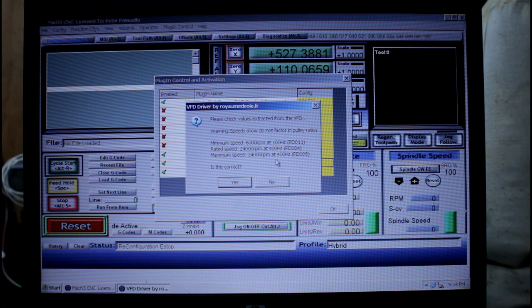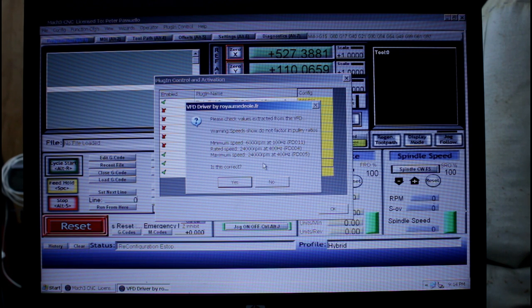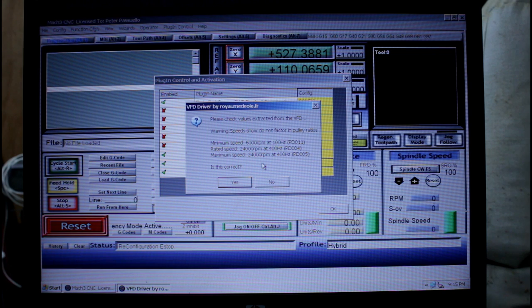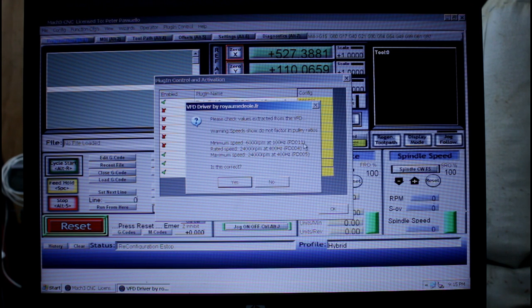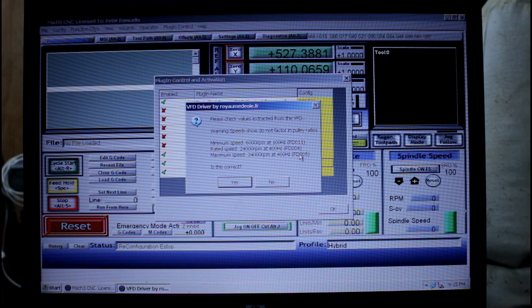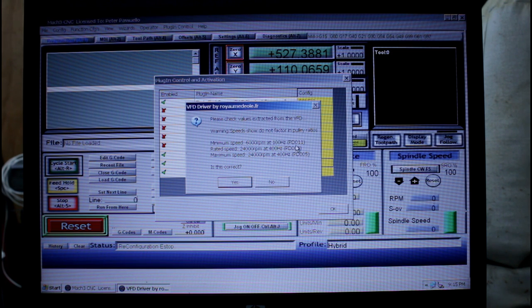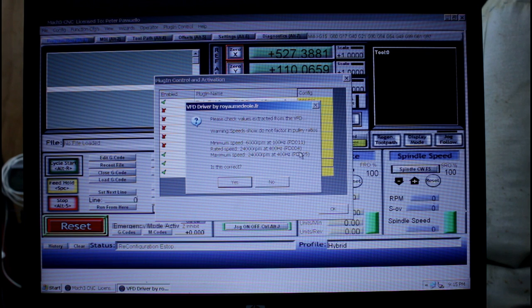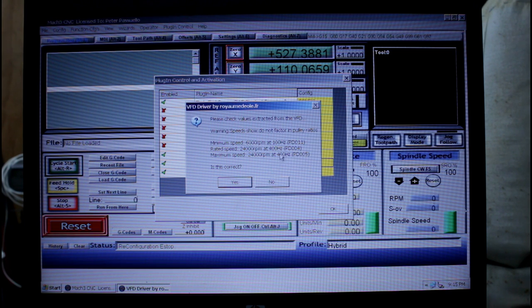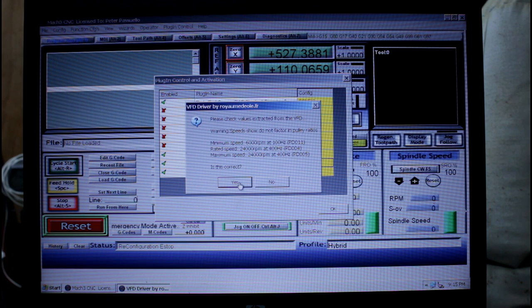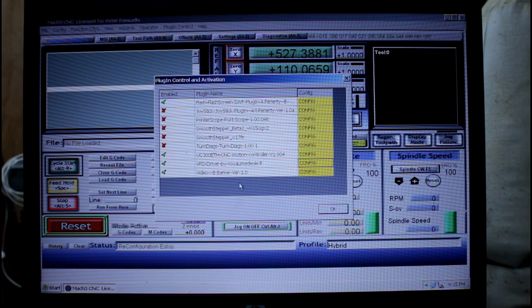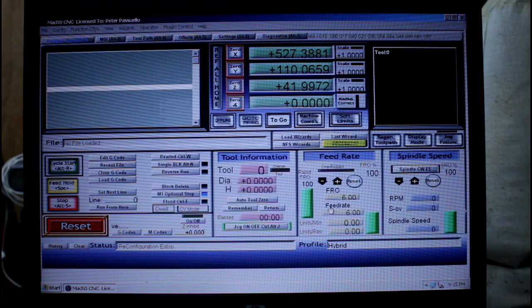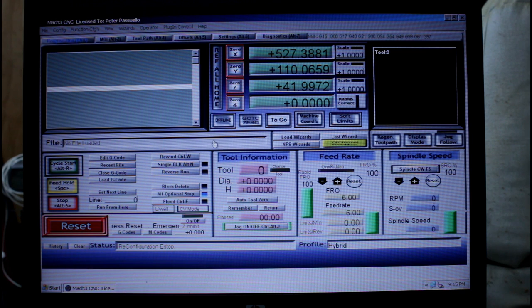And this is why we needed to have our adapter connected to the VFD drive before we proceeded, because now the plugin goes and reads some various registers off of the VFD drive, in this case register 11, 4, and 5. Check that these are correct and in my case they are and go yes. OK, and now we can proceed on.